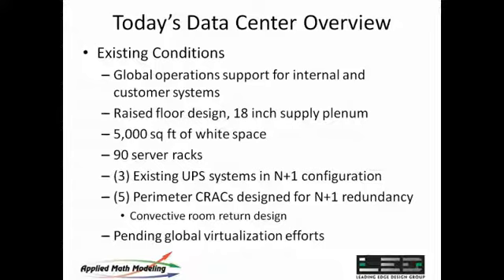Infrastructure-wise, it's a pretty typical design that we'd consider a legacy data center: about an 18-inch raised floor, about 5,000 square feet of white space, and 90 or so server racks. Over the years they had grown to 3 individual UPS systems to maintain an N+1 configuration. The cooling strategy was perimeter CRAC units, 5 of them, designed to provide N+1 redundancy. From a global operations perspective, they had significant IT projects, specifically virtualization efforts, that were pending and being delayed because of problems in the data center. That's essentially the existing conditions as we found them when we started the project.